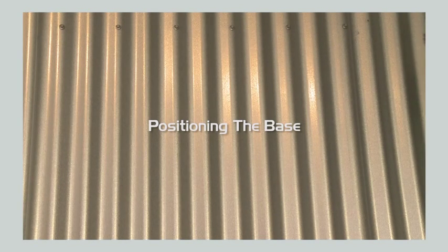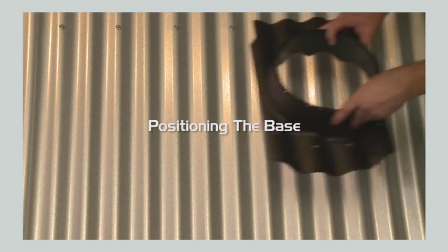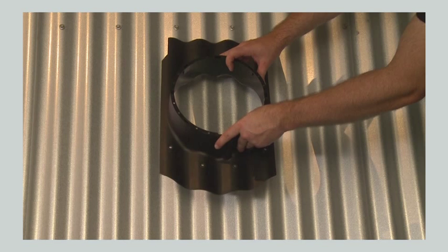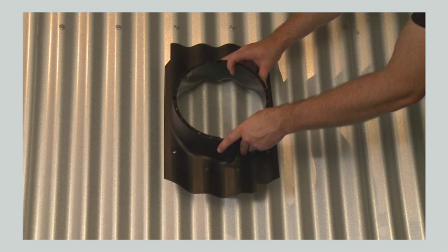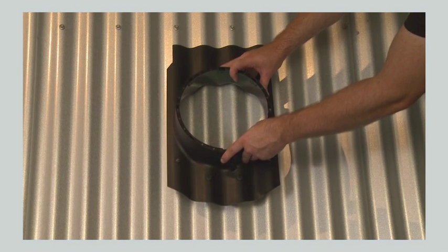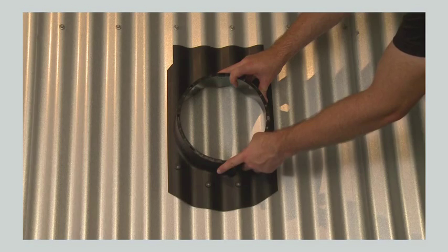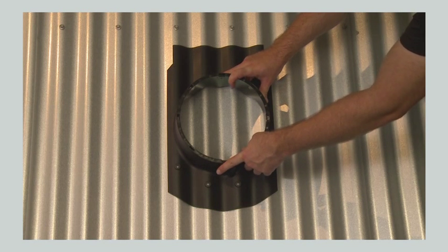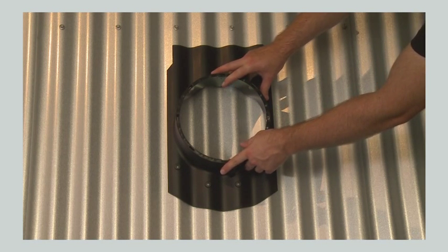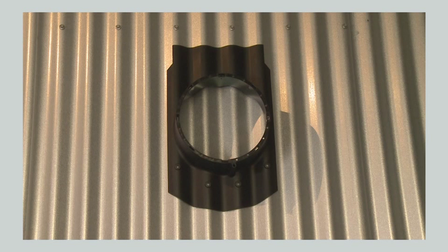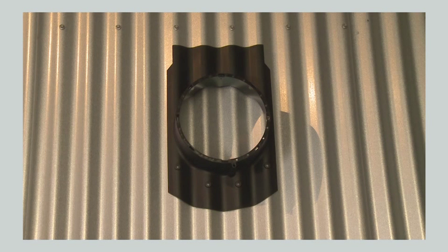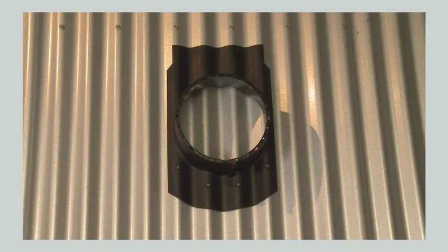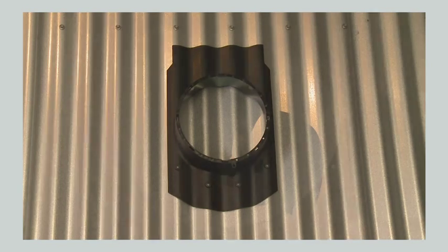Centrally locate the base between roofing screws to avoid the battens with the rounded edge facing down. The shape of the base will stop it from moving left to right and makes a perfect template. It is advisable to check the location of the solar fan unit from within the roof cavity to ensure that the unit is not placed over a joist or strapping. Neither will prevent installation but they may impede airflow and efficiency.